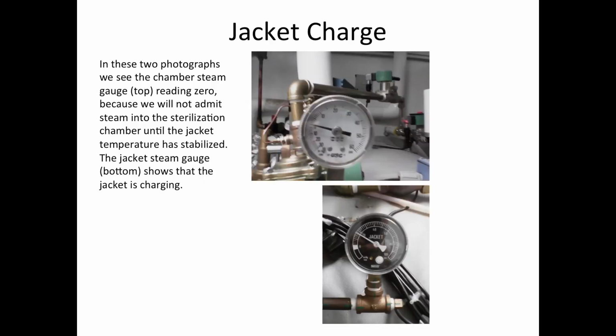And just to drive the point home that the jacket charge is charging only the jacket and not the sterilization chamber, I have a picture of these two steam gauges. You'll notice that the jacket steam charge is up around 20 pounds per square inch, but the sterilization chamber pressure is around 0.